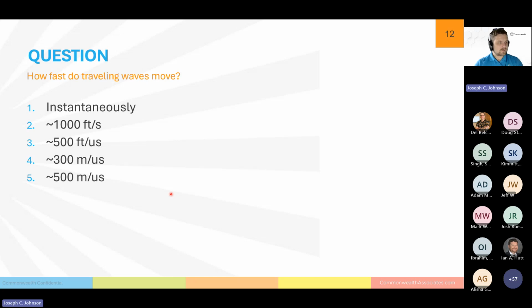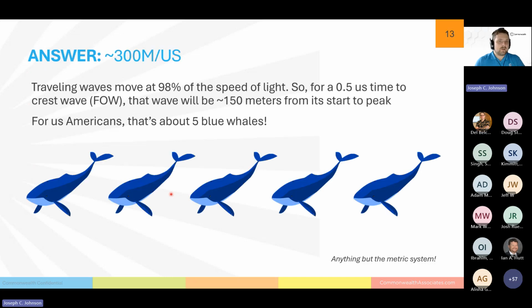All right. So the correct answer is 300 meters per microsecond. So traveling waves move at about 98% of the speed of light. The first answer, 1,000 feet per second, that's sound at standard temperature and pressure. And that last answer, 500 meters per microsecond, is faster than light. So Einstein says that's not possible. But 300 meters per microsecond, for that half microsecond front of wave, one of our fastest waves, that's 150 meters from where the wave starts till it hits its peak.